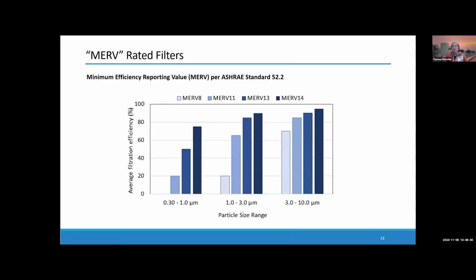How the impact of this technology depends a lot on the type of filtration you're using, because we're recirculating a large portion of our air anytime we're not in an economizer or ventilative cooling mode. So I just wanted to remind everybody or point out, if you're not aware, MERV 13 filters are pretty common today, and they're available with low filtration resistance. And so with a MERV 13 filter in this hardest to remove particle range, we can remove about half of the particles on every single pass, whereas with MERV 8, we can't remove any.